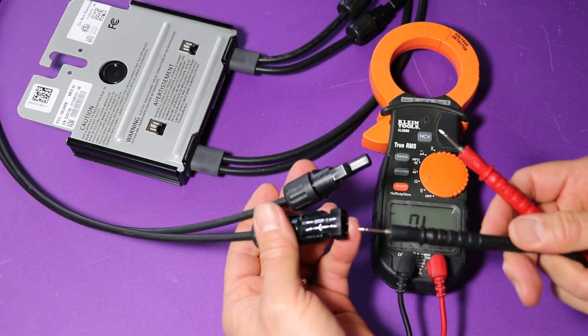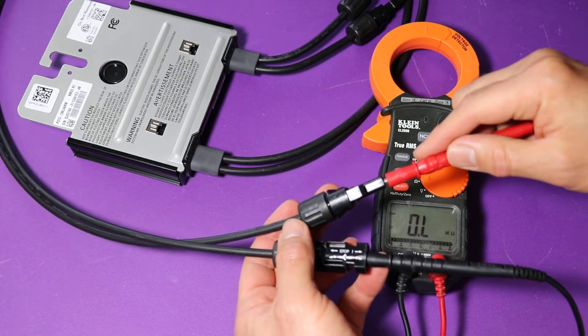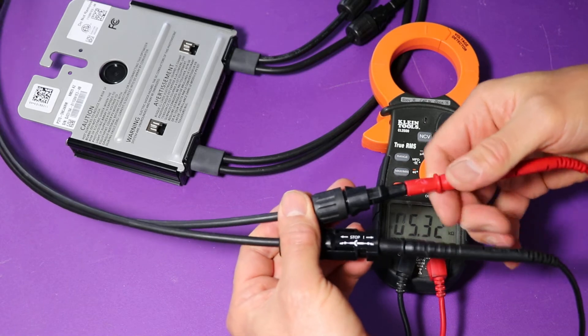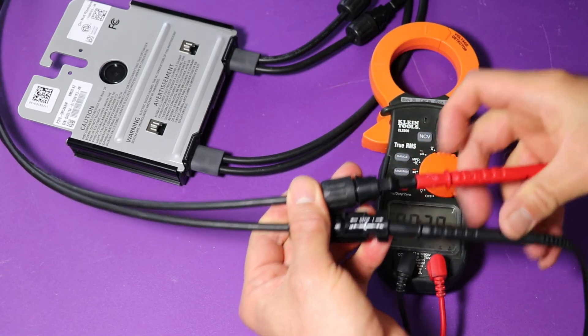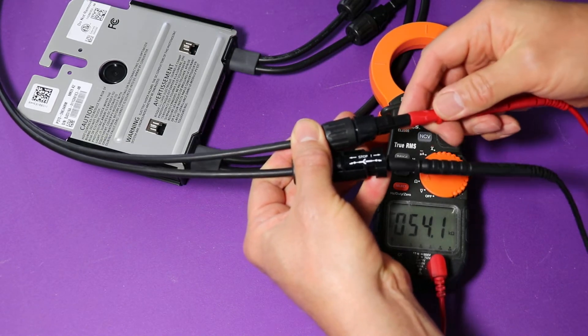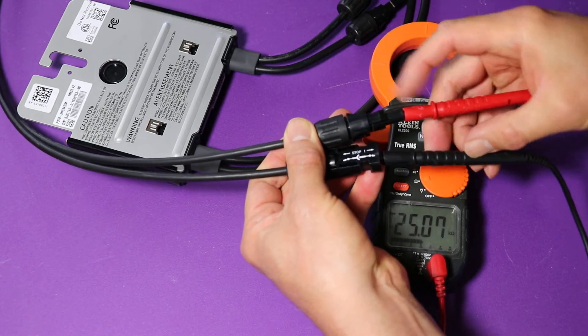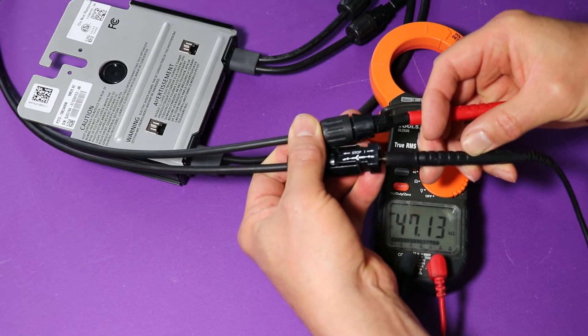Start with the long leads. Once you put the probe inside of the MC4 connector, you want to make sure that there's contact inside in the ferrule. Sometimes that means you actually have to twist it or put some pressure on it at an angle, so the probe will actually be making contact. If you're getting something close to zero, that means you've got continuity.